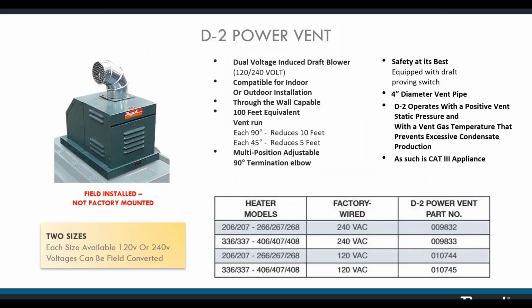There may be installations where, because of the length of the run or other factors, the heater can't be sufficiently vented without help. The help is the D2 power vent. You can think of the D2 as a pump for heater fumes. The flue gases are now forced out through a smaller 4-inch duct. This means you now have a positive vent pressure, and your venting must now be category 3 stainless steel with sealed seams from the D2 all the way to the termination point. That means you can't just run the D2 and put this 4-inch vent up to the hole in the ceiling where the vent normally would be. You can, however, use that existing vent as a chase to run the 4-inch vent inside of.